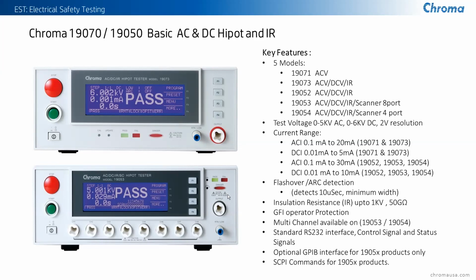All of our products offer what's referred to as flashover arc detection. We're going to cover that in a little more detail. This is a better way of doing the actual flashover or arc test, compared with how a typical hipot test might perform it.